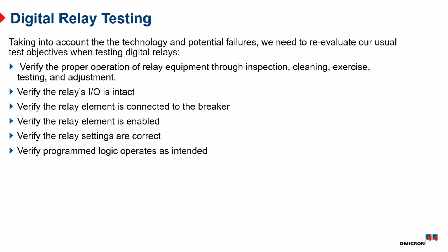So digital relay testing, taking into account how they fail and the technology that we have, the old standard here, verifying the proper operation of relay equipment through inspection, cleaning, whatever, really doesn't fit the technology anymore. Now we have additional or different requirements. Verify the I/O is intact. Verify the elements connect to the breaker. It sounds silly, but you would be surprised at how many times I go out to test a relay and find that there's something wrong with the trip equation, something wrong with the mapping, and the breaker doesn't open when the relay trips. No good.